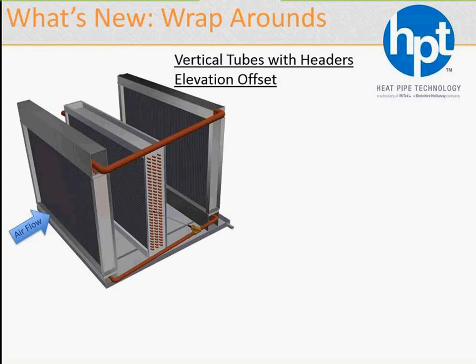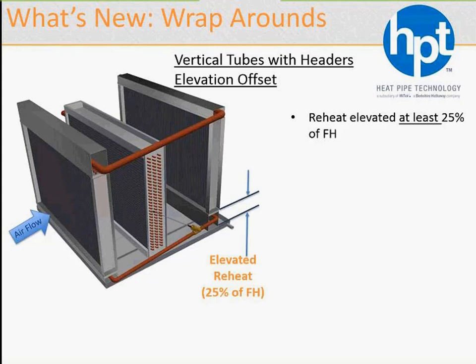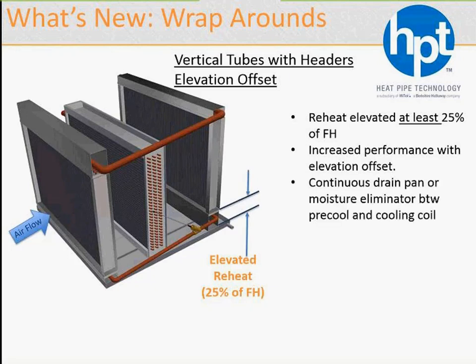How can we improve on the performance of this particular product? As we said earlier, angle inclination goes a long way. So if we elevate the reheat heat pipe by a quarter of the coil height, we start getting some serious performance enhancements. You see here, the reheat heat pipe is sitting on a little platform, so it's about 25% higher, if you like, offset higher than the pre-cool heat pipe. Same construction, a vapor line on top, liquid on the bottom, with a valve on the liquid line. Performance increased, and we'll show you the difference in performance between without an offset, or level, the previous slides, and this particular one with an offset up to 25% of coil individual height.